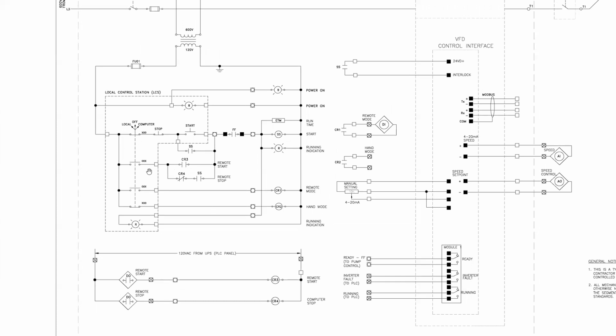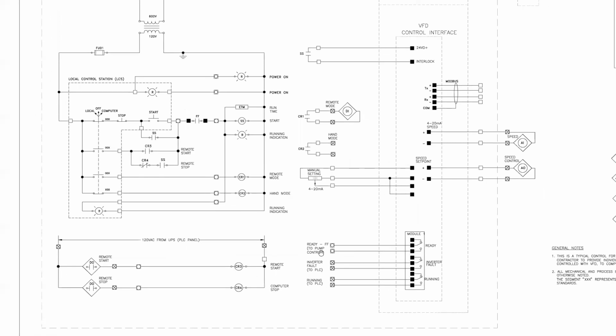When this switch is in computer or remote, we can then see that the CR3 will start the pump. So CR3, when we find down here, is connected to the DO start, and CR4 is a DO stop command. So for this system, it looks like the pump has a pulse to start and a pulse to stop output. So there are two outputs wired back to the PLC.